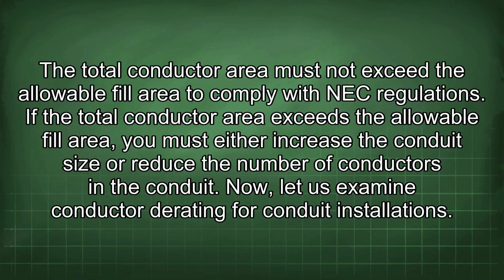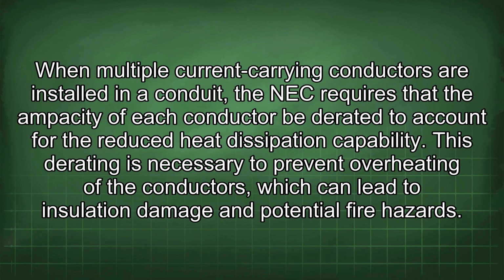Now let us examine conductor derating for conduit installations. When multiple current-carrying conductors are installed in a conduit, the NEC requires that the ampacity of each conductor be derated to account for the reduced heat dissipation capability. This derating is necessary to prevent overheating of the conductors, which can lead to insulation damage and potential fire hazards.